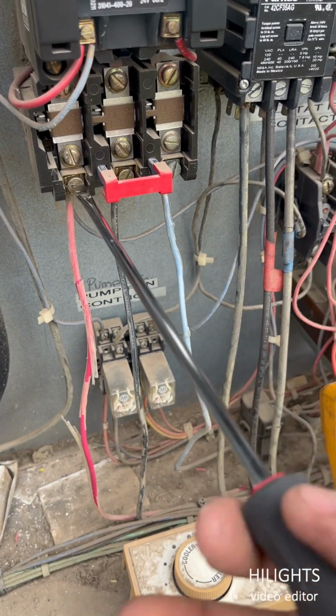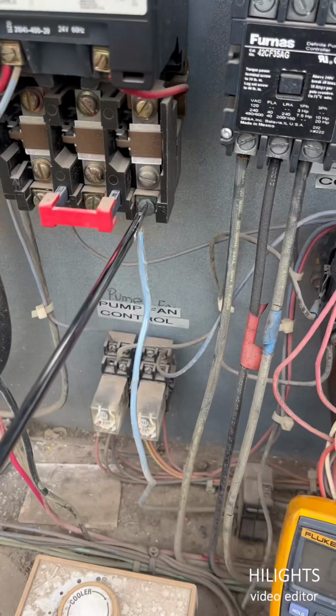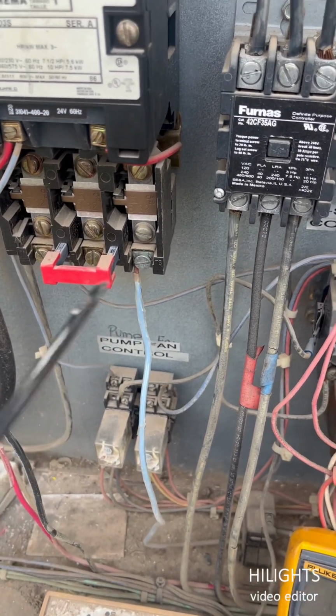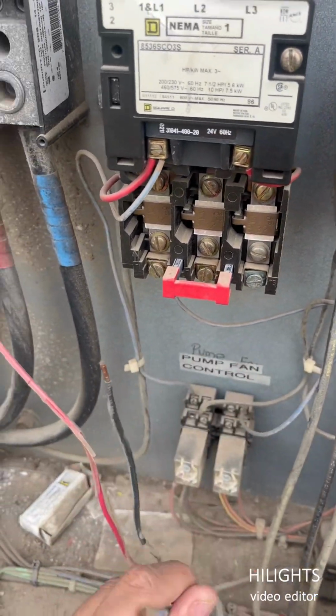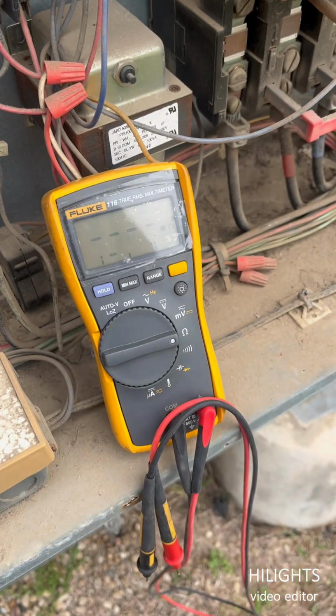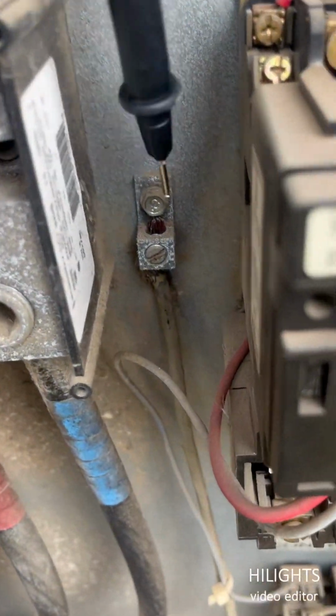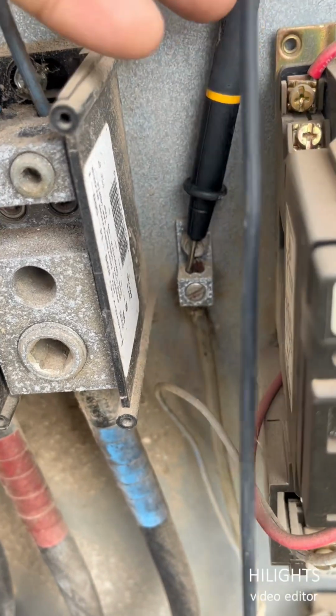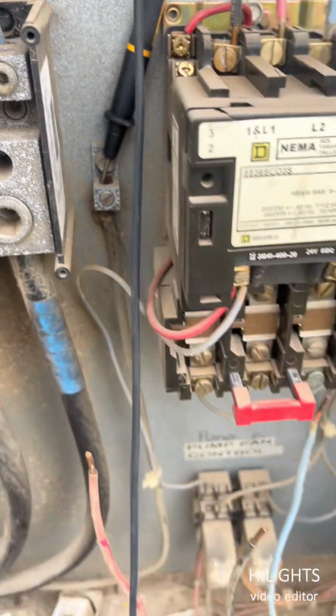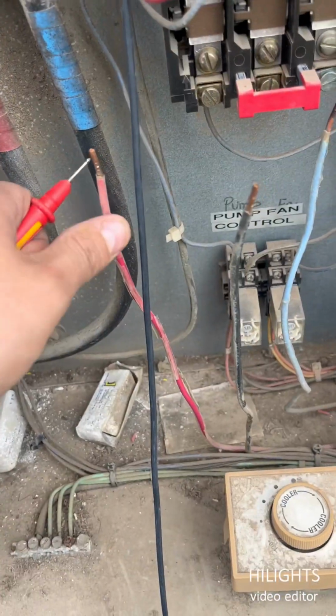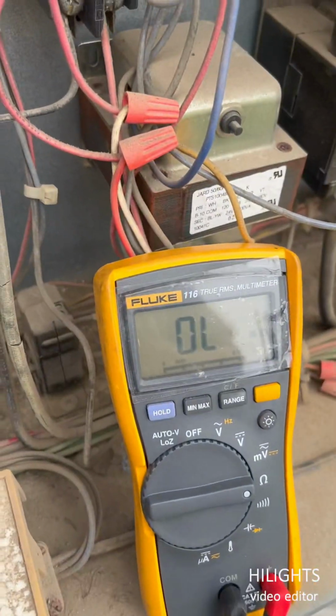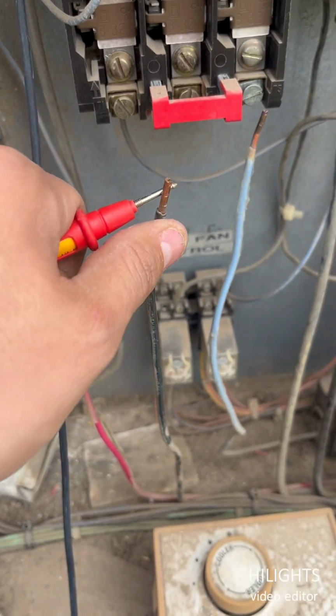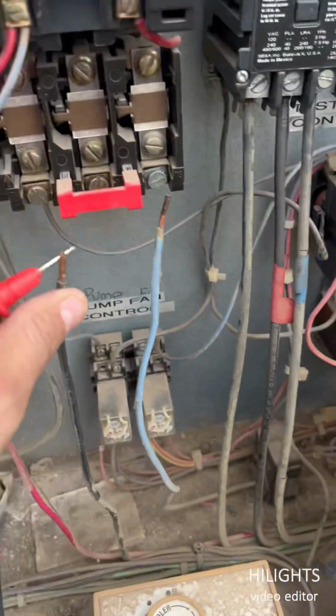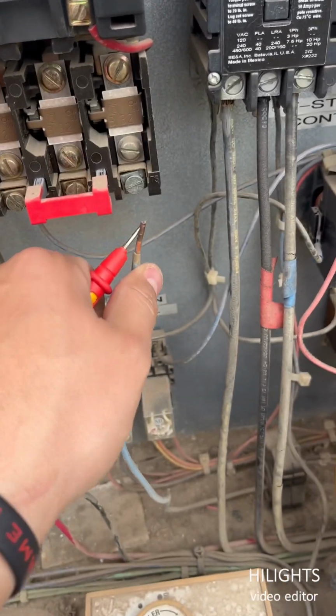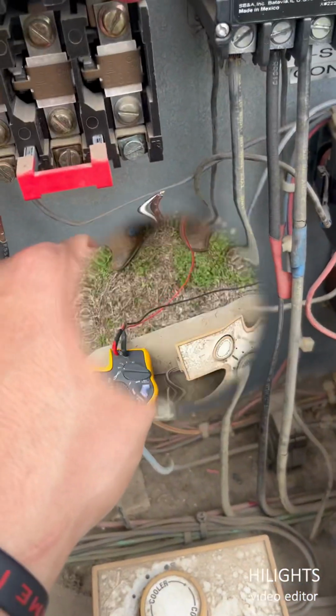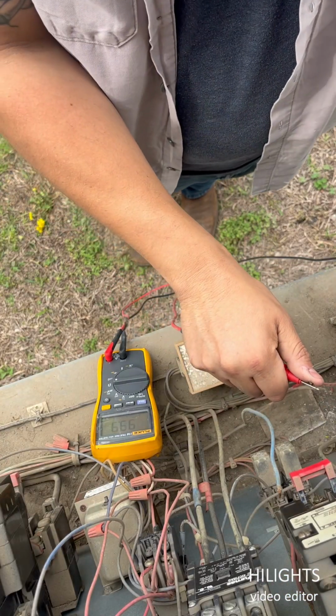Alright, so what we're gonna do, we're gonna disconnect the wires coming from the pump, and then we're gonna test it. We're gonna test at the ground, make sure it's not short to ground, and then we're gonna ohm it out between each legs. So I'm gonna place one of my leads on the ground, because we're gonna test the continuity to ground. So you should not get continuity to ground. So I should be reading OL right here. Yep, OL. Go to the next one. OL, that's good. And OL. Now remember, if you were to get a reading from one of the legs to ground, then that means it's shorted.